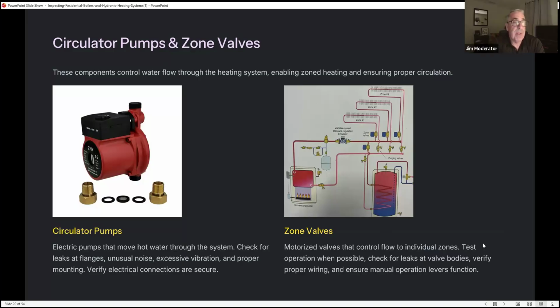Circulator pumps and zone valves. These components control water through the heating system, enabling zone heating to ensure proper circulation. Circulator pumps, electric pumps that move hot water through the system. Check for leaks at flanges, unusual noises, excessive vibration, and proper mounting. Verify electrical connections are secure. Zone valves, motorized valves that control flow to individual zones. Test operation when possible. Check for leaks at the valve bodies. Verify proper wiring and ensure manual operation levers function.